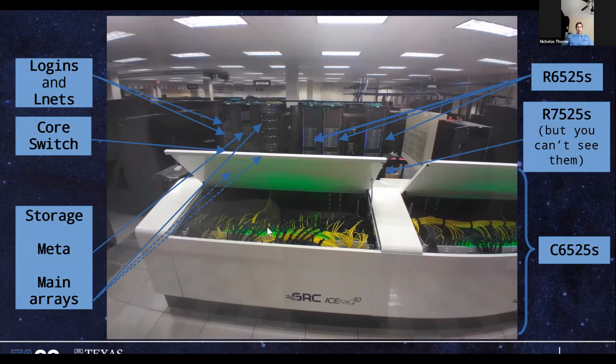We have also noticed, and this is purely our opinion at the moment, we don't have any hard data backing this up, but we have heard similar things from other people also running this, that we get a slightly lower component failure rate with the immersion cooled servers over the air cooled servers. It's not concrete yet, but we suspect that that's the case.